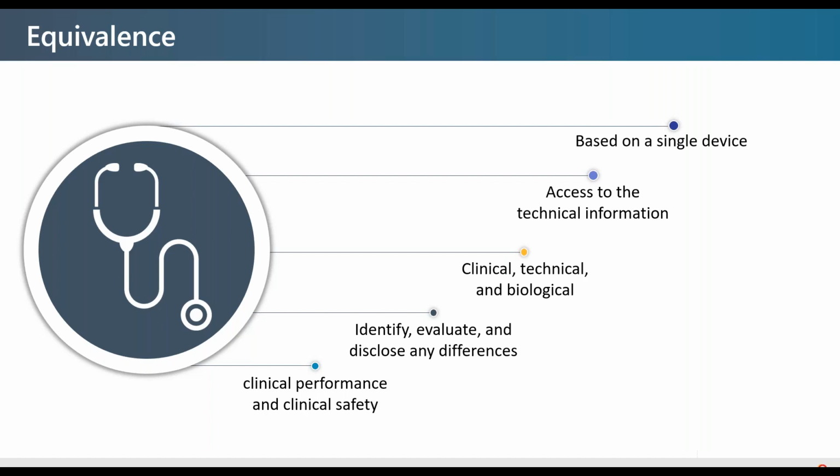The technical has to have similar design conditions. You can have similar flow rates, pressure settings, and tensile strength. Those don't have to be the same. Because a lot of times I'm looking at this and I'm going, well, if all this stuff has to be the same, isn't it the same device, and that can be our hurdle, right? How much different are we doing? So usually we're just improving the same device and adding a higher flow rate, or higher tensile strength or something like that.